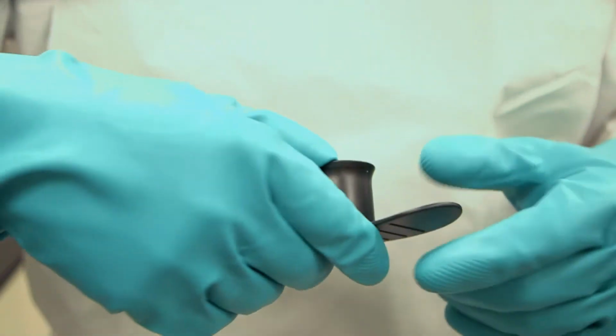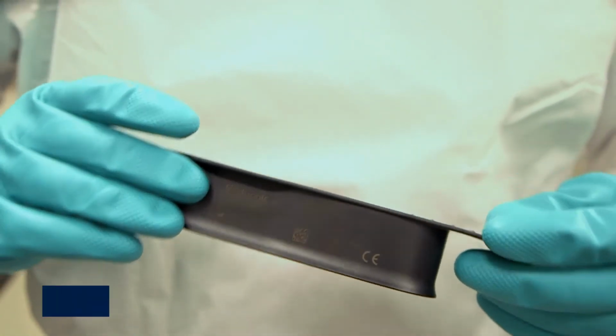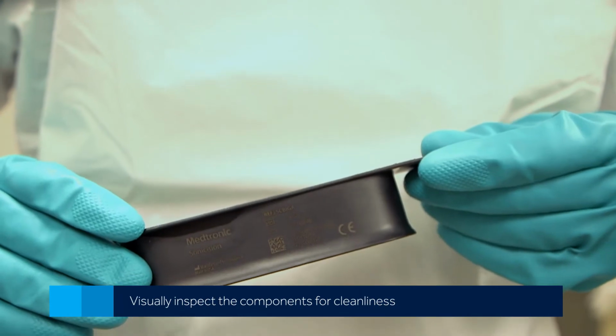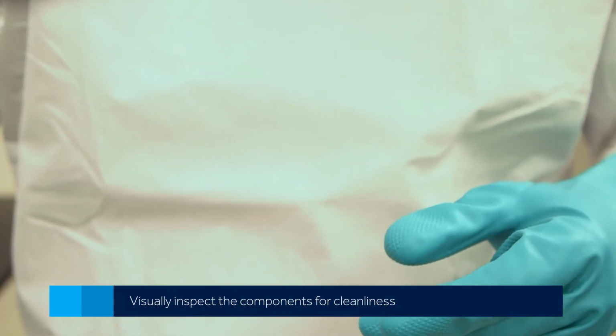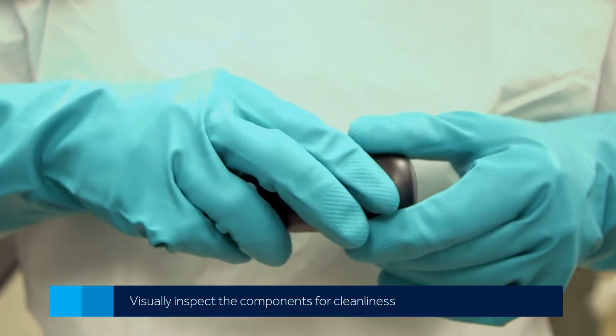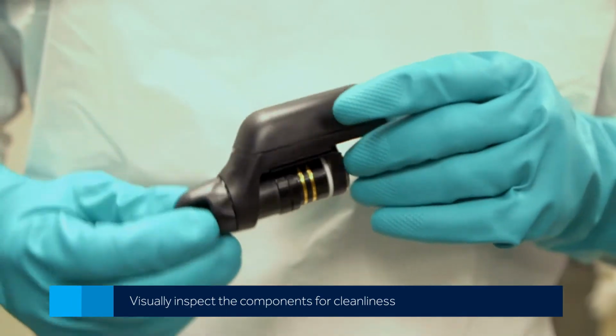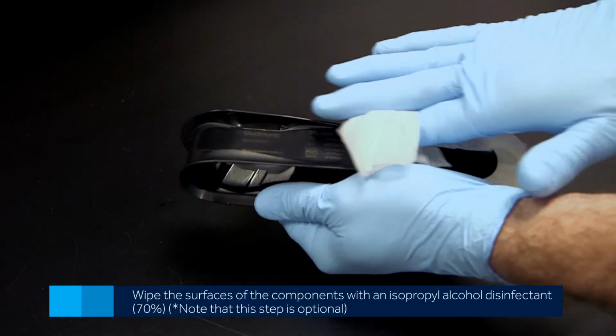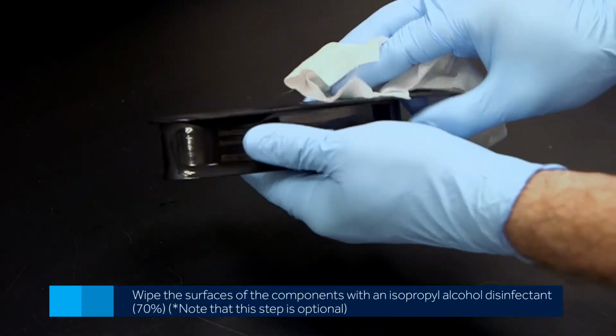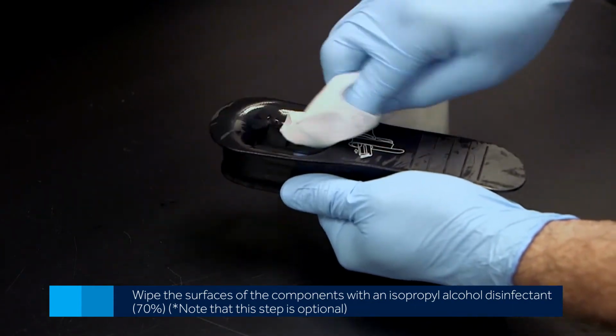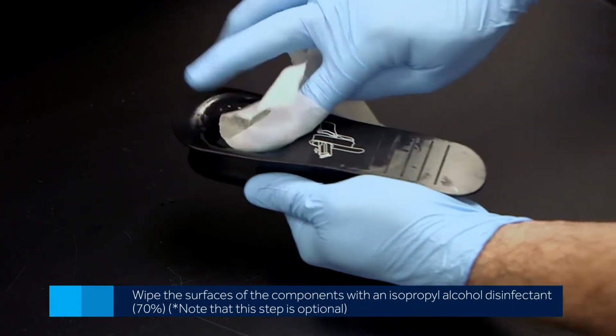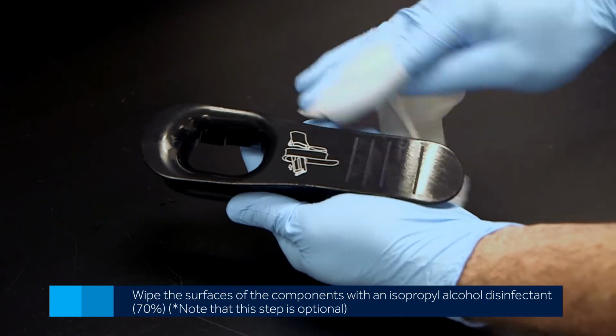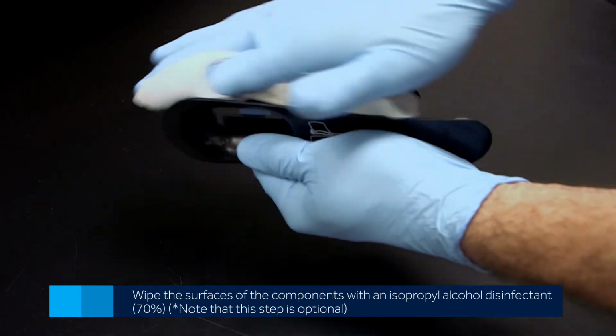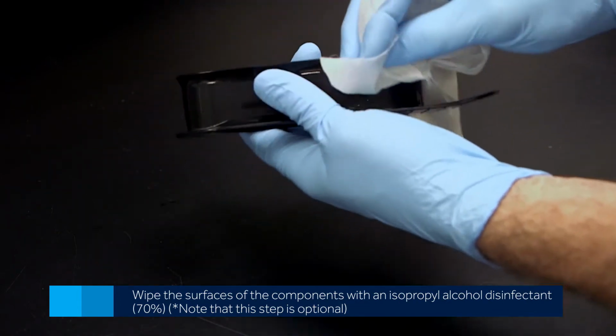After completing manual or automatic cleaning, visually inspect the battery insertion guides and generator for cleanliness. Repeat the cleaning cycle if necessary. In facilities that require disinfection before sterilization, wipe the surfaces of the battery insertion guides and generator with an isopropyl alcohol disinfectant, 70%, after manual or automatic cleaning.